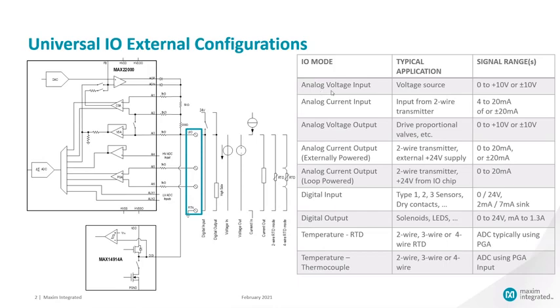Which supports voltage input 0 to 10 or plus minus 10 volts, current input either 4 to 20 milliamps or plus minus 20 milliamps, analog voltage output 0 to 10 volts or plus minus 10 volts, current output with external 24 volt field power, either 0 to 20 milliamps or plus minus 20 milliamps.